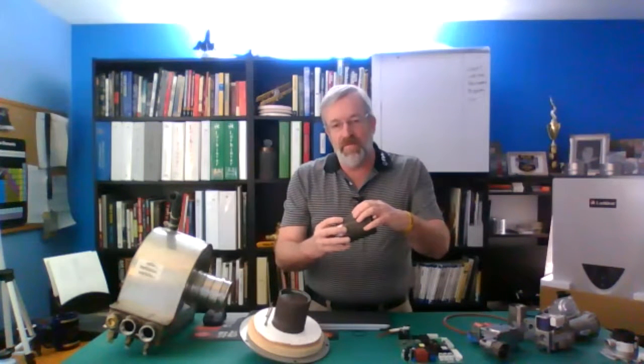The way the combustion works on these is, I bring that gas-air mixture in through them, same here, and I bring it out of my burner and spark it here. My combustion is not particularly on that burner. It's almost off that burner, and it's a glow, if you will. It's not a flame. We refer to it as a flame, we talk about it as a flame pattern, but it really is more of a glow that you'll see at low fire, an orange glow. As I ramp up, I'm going to get some blue in there, and I'm going to see some orange specks. So it's really important to see that, and a consistent flame pattern all around. We don't want to see a big blue flame. We don't want a big ball of flame, stuff like that. So it's just important to know that that's what it's going to look like.